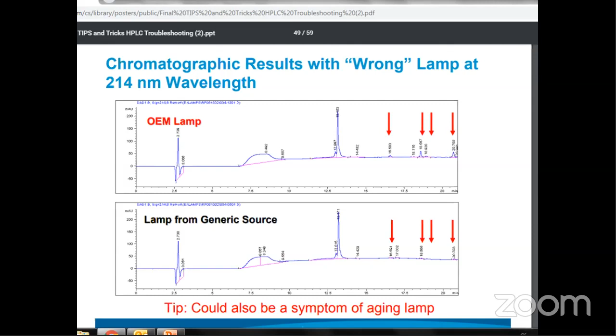Again, this slide presents the same thing we discussed before. Here it is highlighted more precisely with respect to signal to noise ratio. When you are using a very good lamp recommended by the vendor, and we are considering a good detector, you will find the peak of interest has good sensitivity in the method. While when you go with the generic source, the first thing is your baseline is disturbed, followed by the loss of sensitivity.